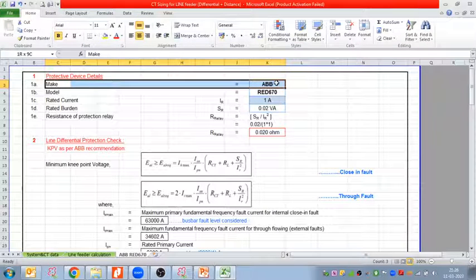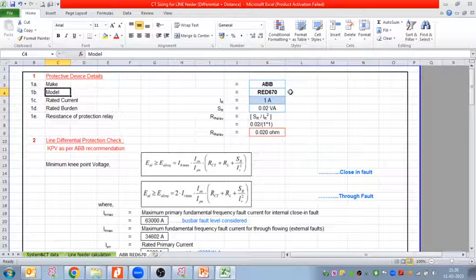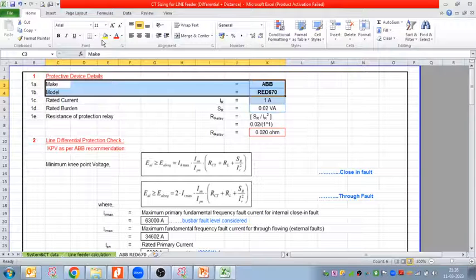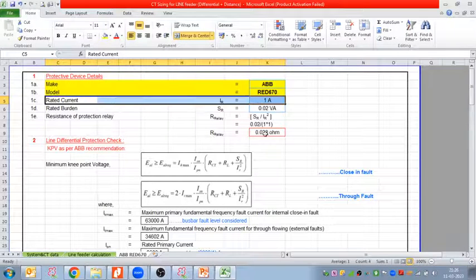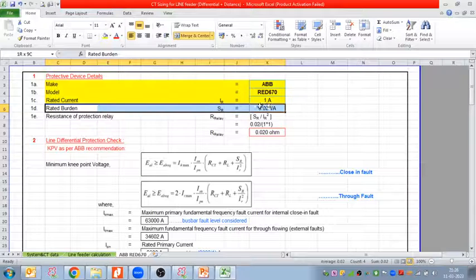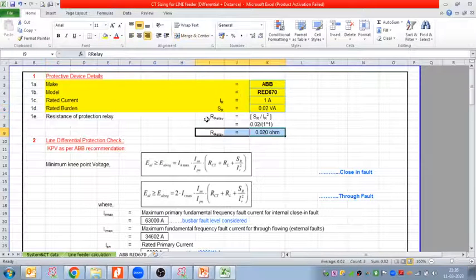The make of the relay we put here, then model RED670. These two cells are clear to everyone. Rated current, the relay rated current, means the relay is connected on the CT secondary side. The secondary current is 1 ampere, so the relay current would be 1 ampere. The relay burden we can take from the relay technical manual, or the relay burden is also given in the application manual. Because the burden is in VA and you know the current, you can calculate the resistance of that relay, how much resistance it will offer. So these four cells are clear.